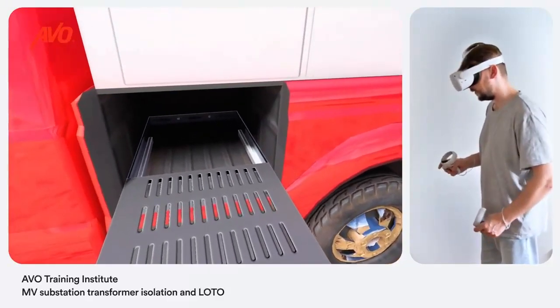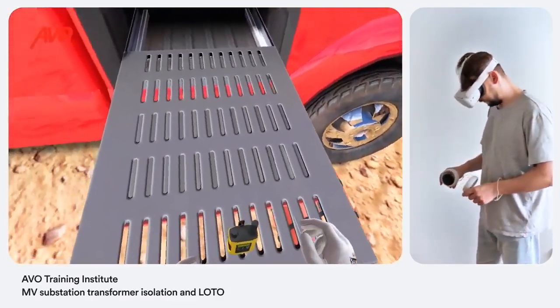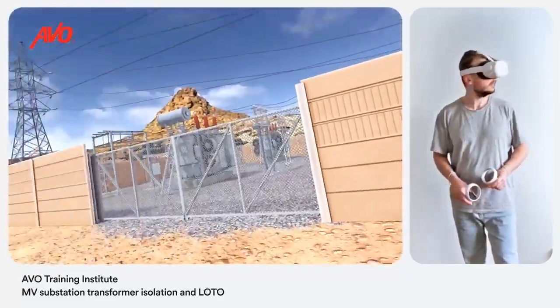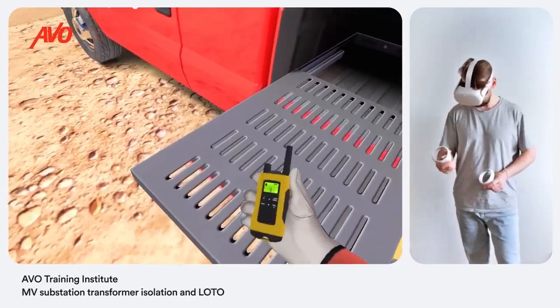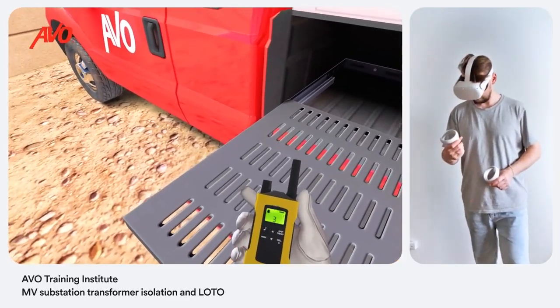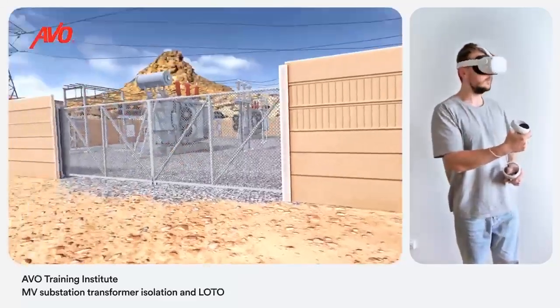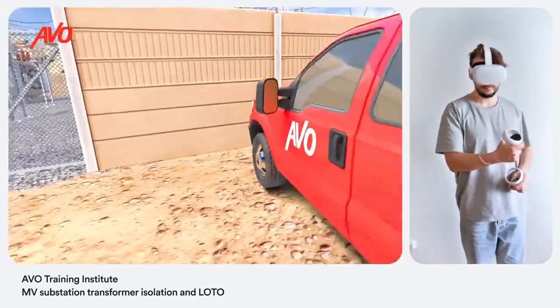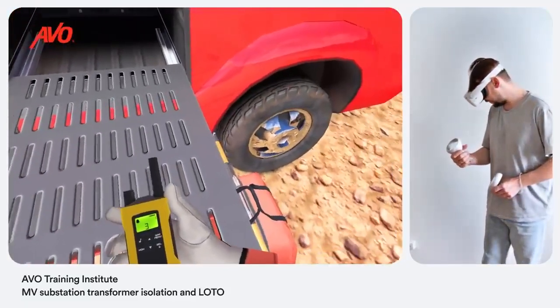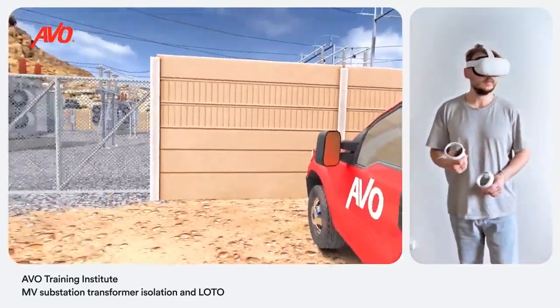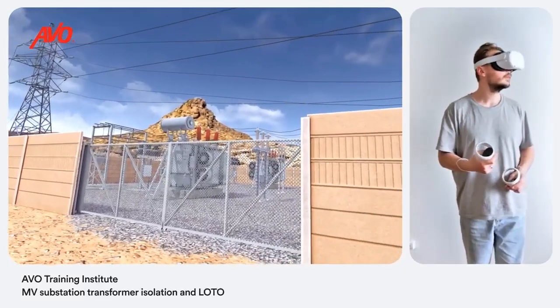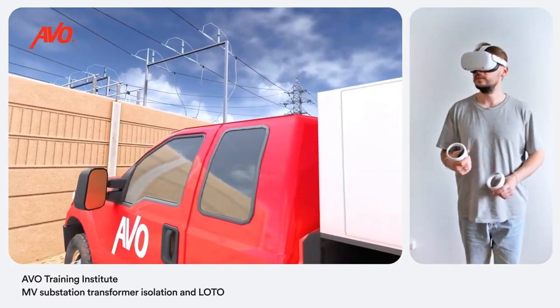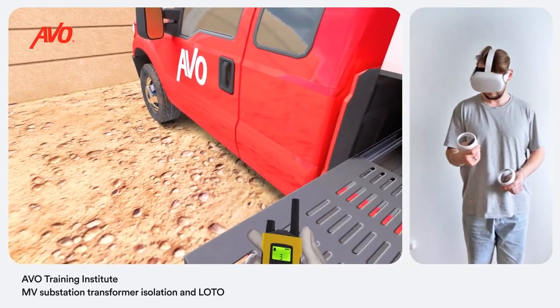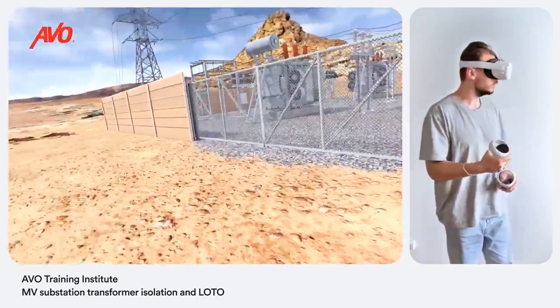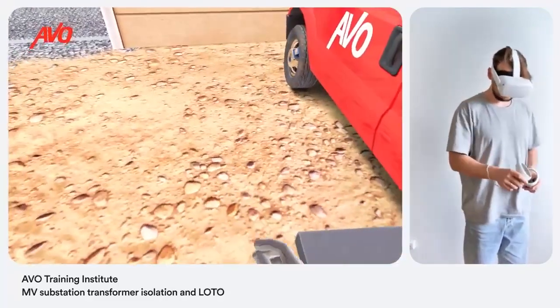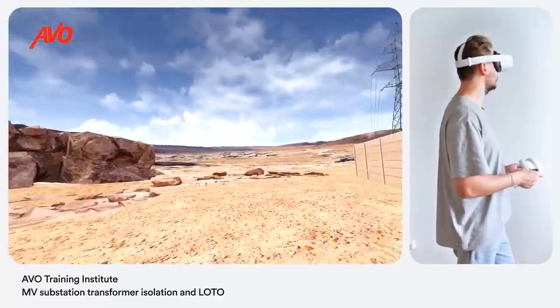Now you need to obtain proper authorization through control desk operations to enter the substation. Use the handheld radio to contact the controls. This is Electric 1. Go ahead, Electric 1, this is Control. Electric 1 requests permission to enter the 123 substation at the ABC gate. Electric 1, this is Control. You are cleared to enter Substation 123 through the ABC gate. Please be safe and let Control know when you're on your way out. Roger that, thanks for the help. Once the permission has been received, you can proceed to the substation gate and enter the switchyard.